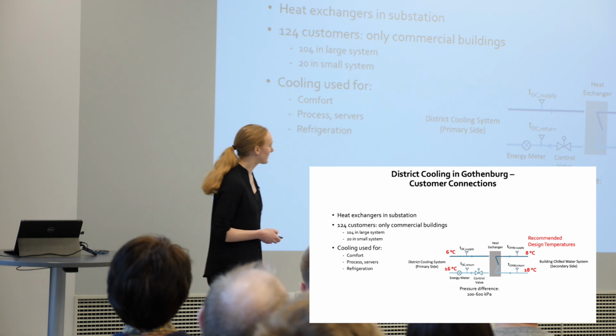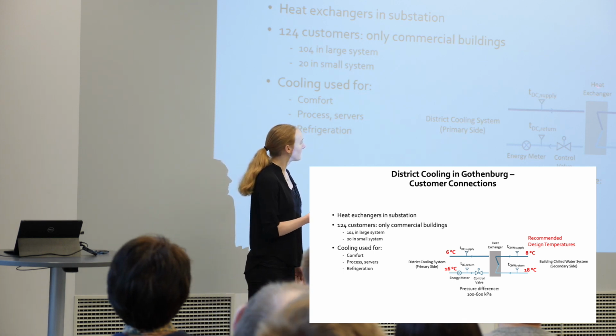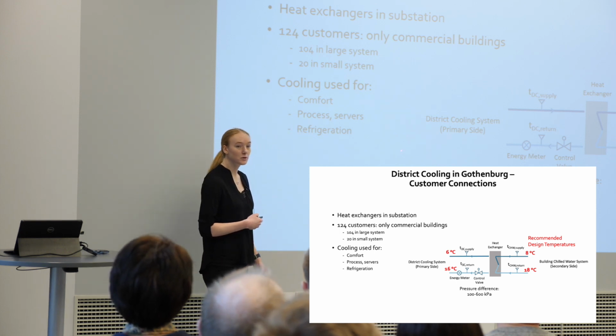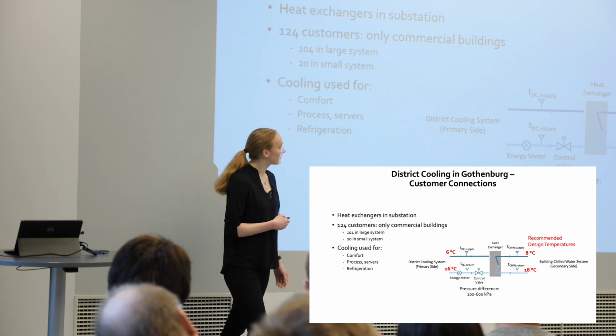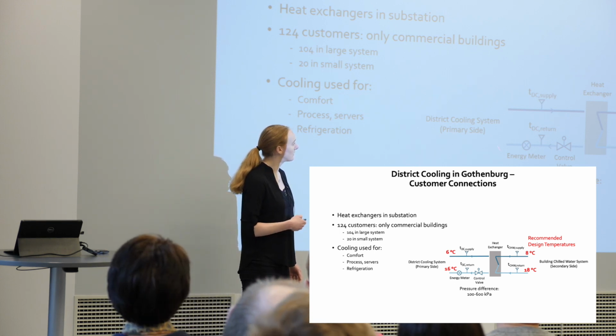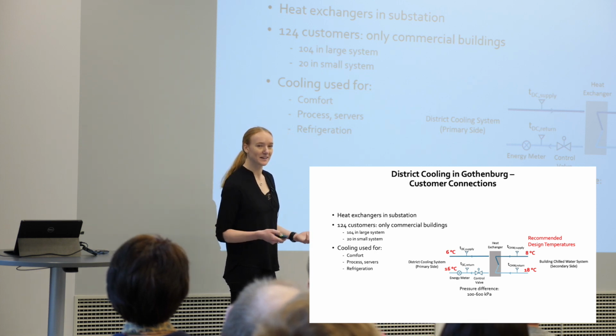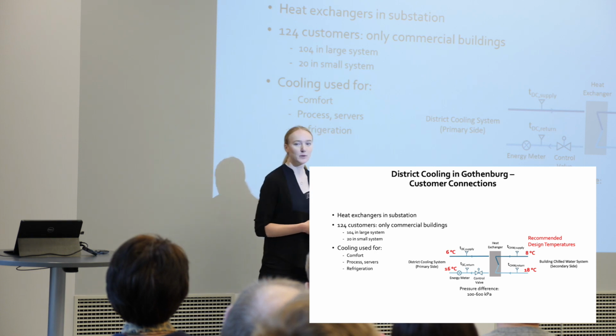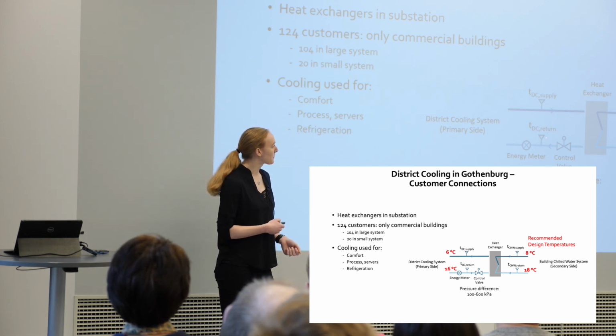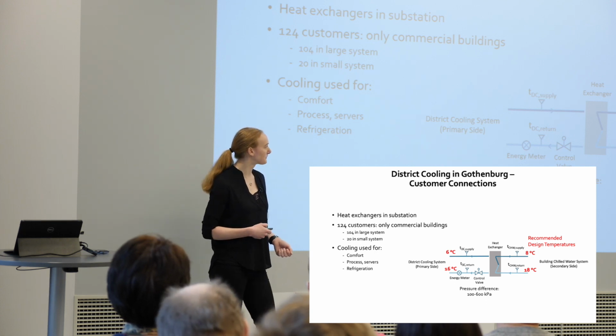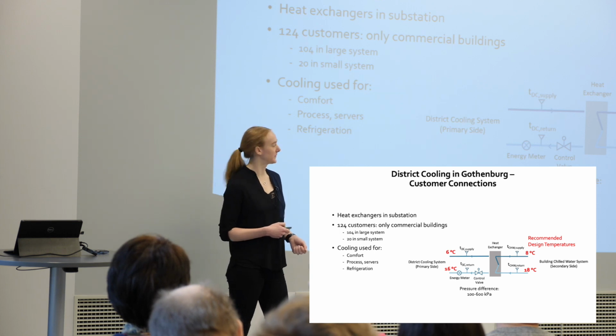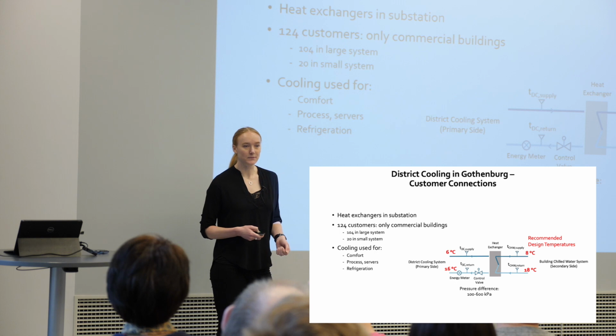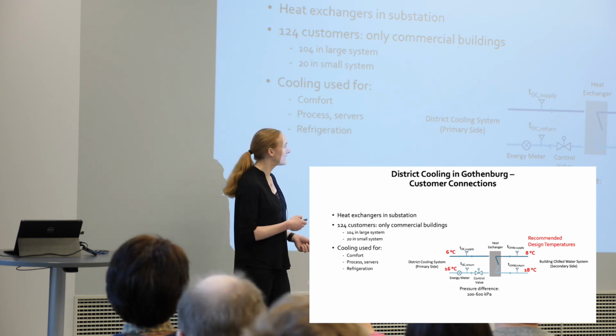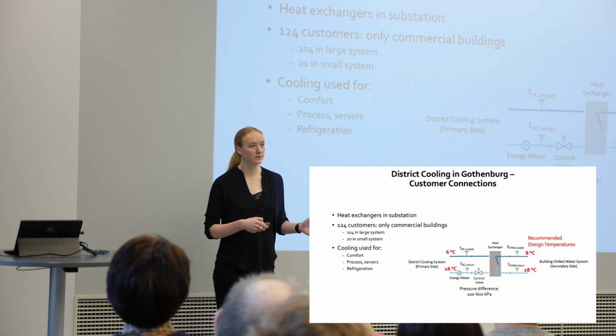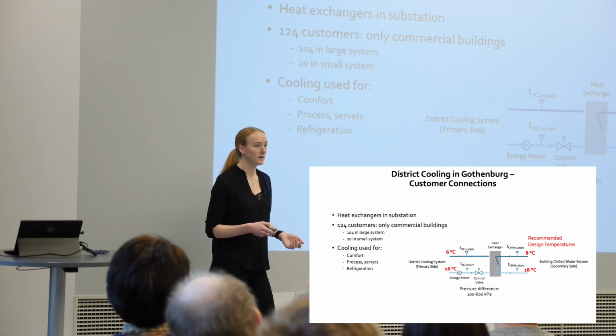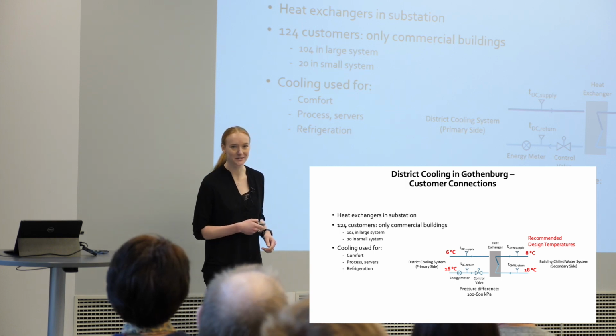And here you can see a schematic of the substation. Here's the heat exchanger, and this is the district cooling or distribution side, which I call the primary side. The equipment installed here is needed in order to send out the invoice to the customers. So the district cooling provider measures the temperatures, supply and return, and also the flow, and calculates the energy in the energy meter. They own this equipment. However, all the customers in the Gothenburg district cooling system own the heat exchanger and the control valve. Compared to the district heating side, where the utility provider owns all the substation and all the equipment, it's the other way around in the district cooling system.